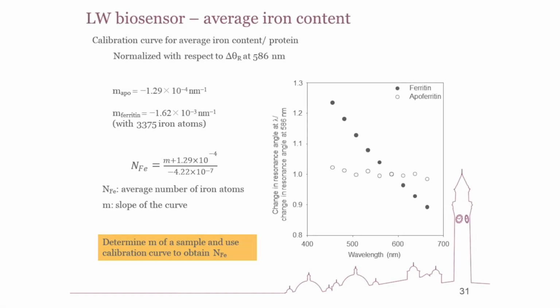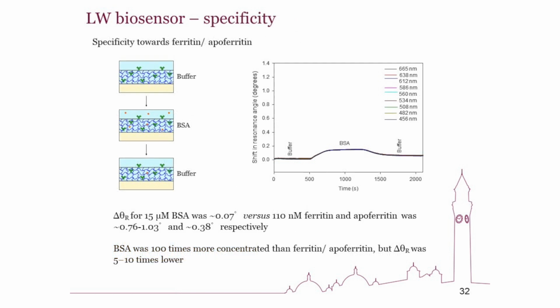Okay. Then there was another calibration curve where I'm plotting the change in resonance angle at each wavelength divided by the change in resonance angle at 586 nanometer. So the open circles are for apoferritin and the closed circles are for ferritin. And the slope for apoferritin is about 10 times lower than that of ferritin with 3,375 iron atoms. And if we have a protein where the iron atoms is in between 0 and this, the slope would be intermediate. So we can write the relationship between the slope of this curve and the number of iron atoms, and it's given by this expression. So for any unknown protein, if we can do the same curve, we can use this relationship to then determine the number of iron atoms.